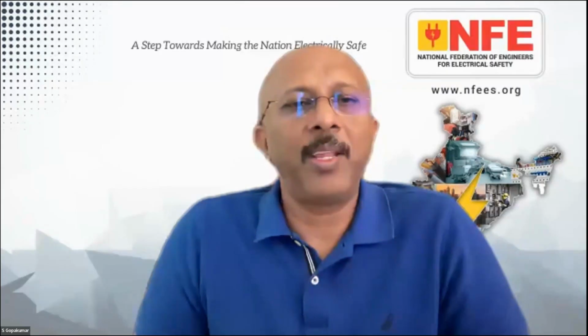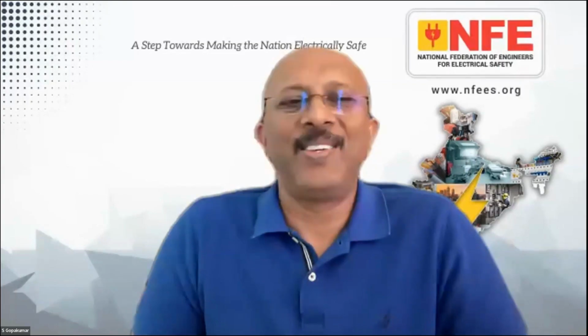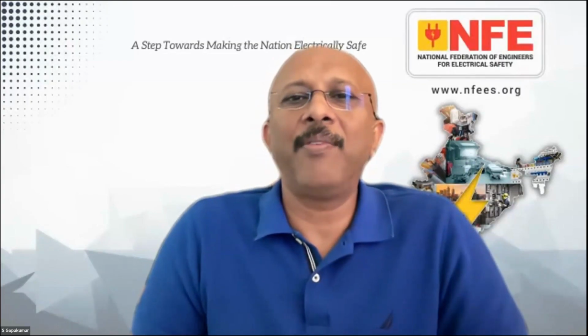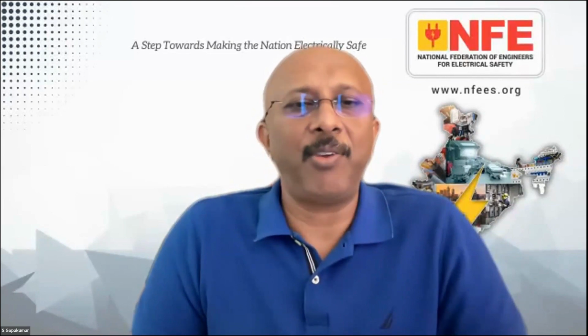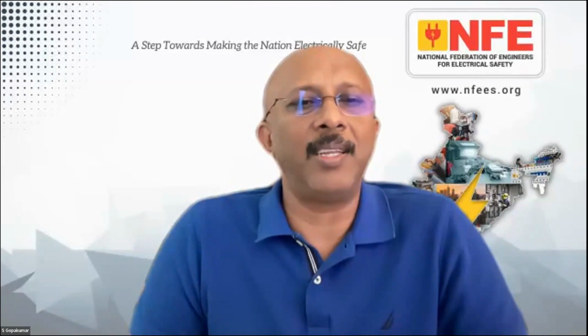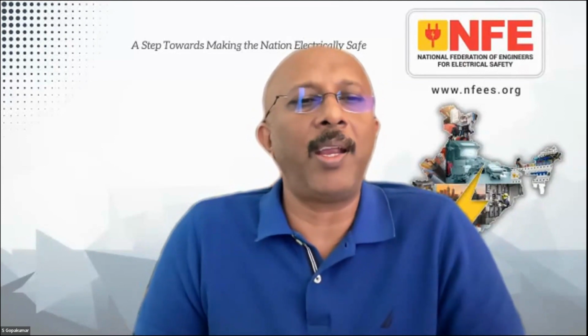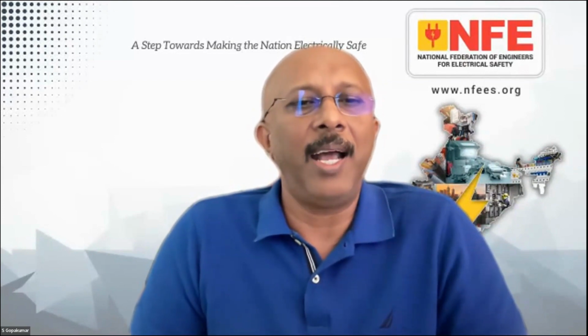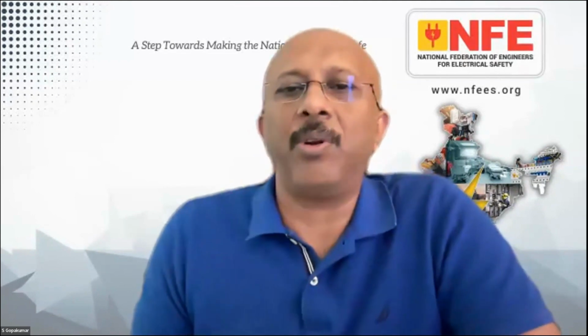I know that there are other rules describing the safety of personnel, and that depends on what type of electrical network we are working on. Maybe some of my pictures weren't clear enough. In the case of insulation resistance, there was a guy measuring floors and walls, and that's on a de-energized object, so that's a different thing. Anyway, we will take care of it. Actually, we face a small problem in India. The gloves rated for a certain voltage are sometimes very uncomfortable to wear and to hold a clip or clamp and do the testing. As a result, I have seen a lot of cases where people try to avoid them, which is not correct.